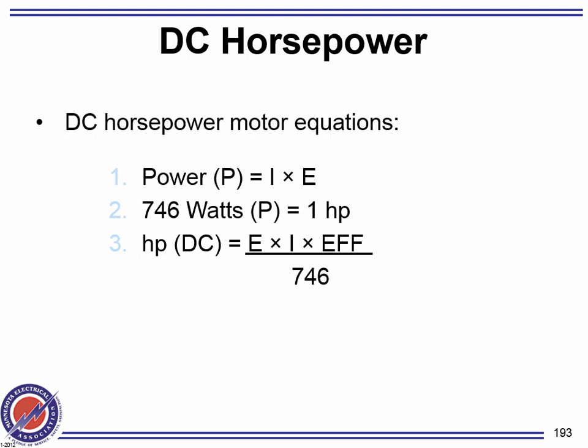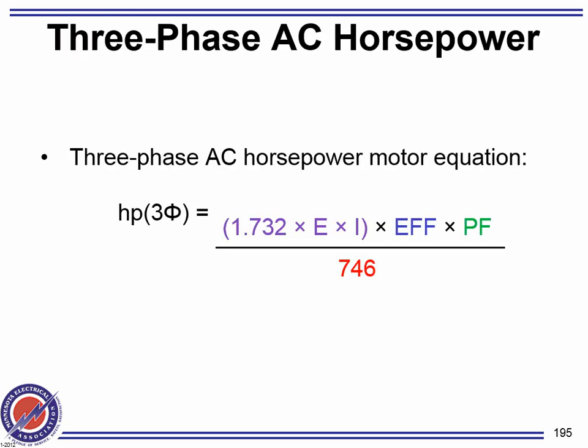And then, gentlemen, we get into the formula that we need to use. Here's the formula that you need to use. I want to remind you guys that this is Ohm's law. Everybody understand that this is Ohm's law? E times I. Anybody can tell me where this component came from? Why is the power factor in the equation? Because when it deals with motors, we always deal with true power, not apparent, not reactive. So I need the true power, then I have to multiply by the power factor. Anybody knows what 746 is? That's the conversion between mechanical and electrical power. Every 1 horsepower is equivalent to what? 746.